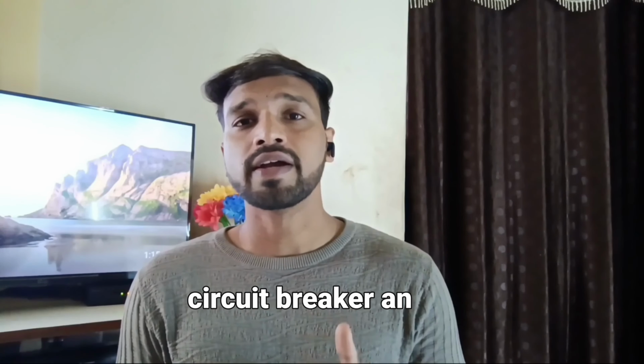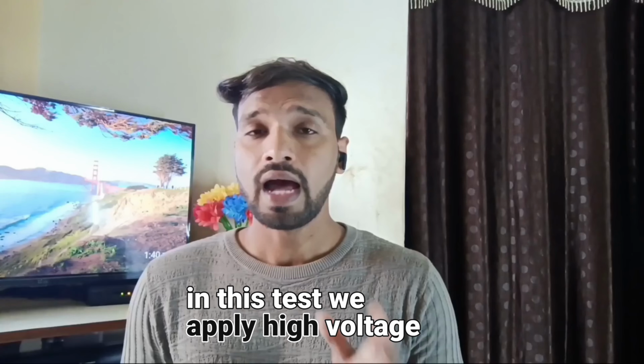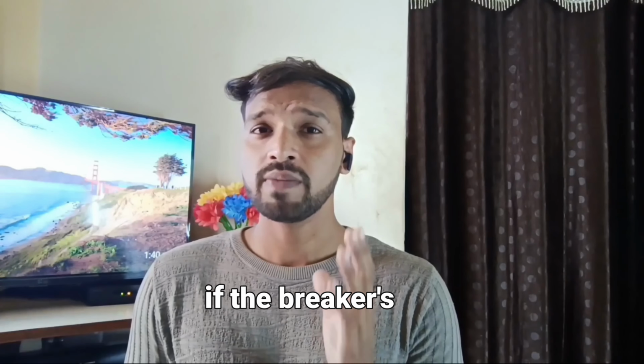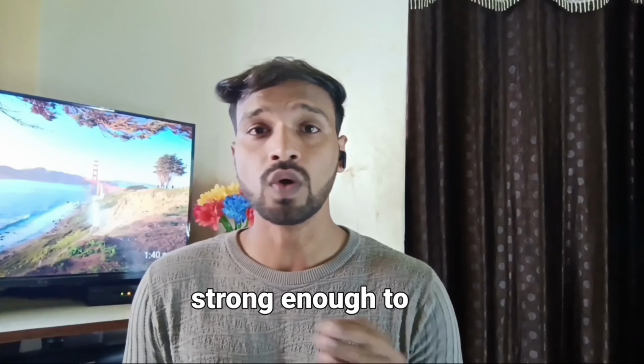So let's talk about the power frequency test. This test simulates the regular voltage that the breaker will face in day-to-day life. Imagine you are lifting weights and you need to hold that weight steady for a minute. Similarly, in this test, we apply high voltage for a whole minute to check if the breaker's insulation is strong enough to hold up. If it is holding up and there is no breakdown and no sparking, then the test is said to pass.